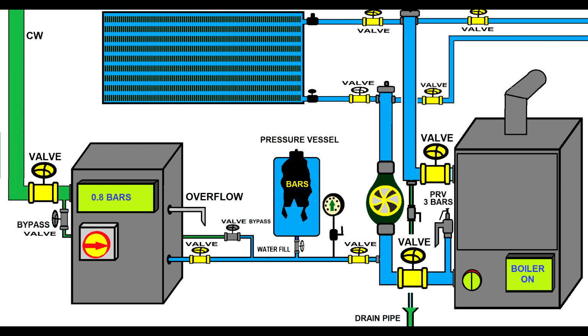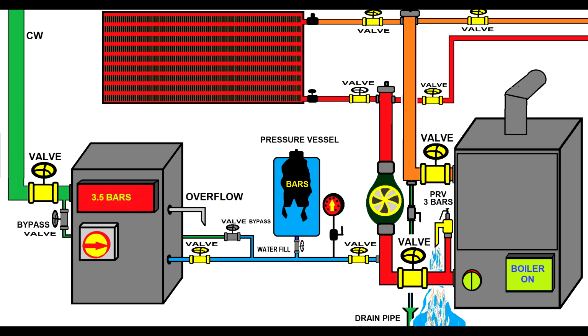If you are unlucky enough to have a bad pressure vessel because the rubber bellow blew up inside, when the system is heating up, the pressure will increase. And if you look at this situation, the PRV near the boiler, you see it is changing color between yellow and red. It can only sustain 3 bars, and the pressurization unit shows 3.5. That's why the pressure release valve allows the water to go out of the system, and at one point the pressure will be balanced because you lose enough water.